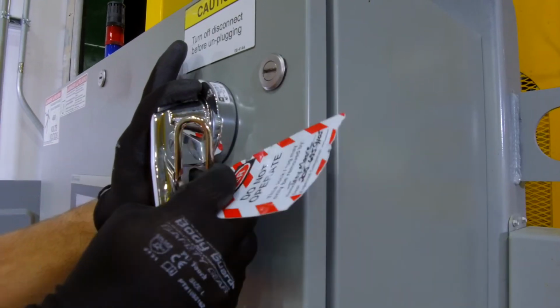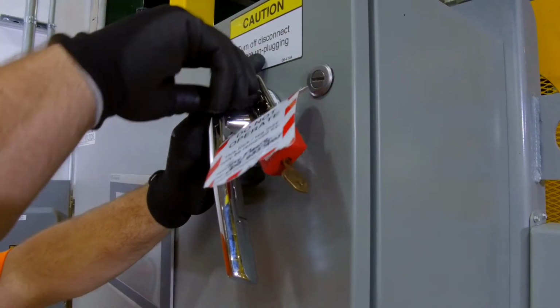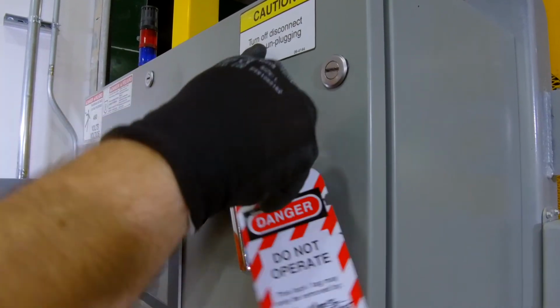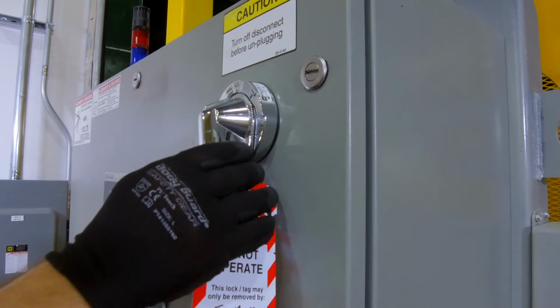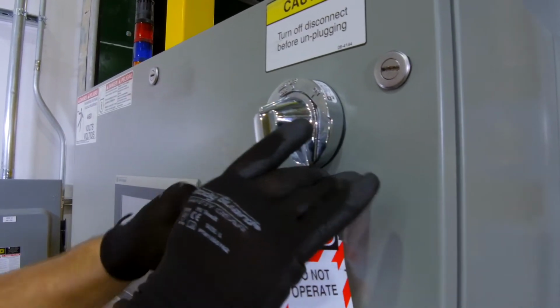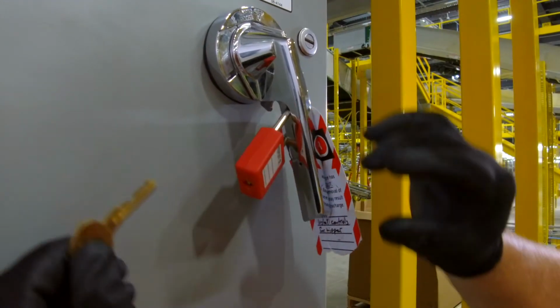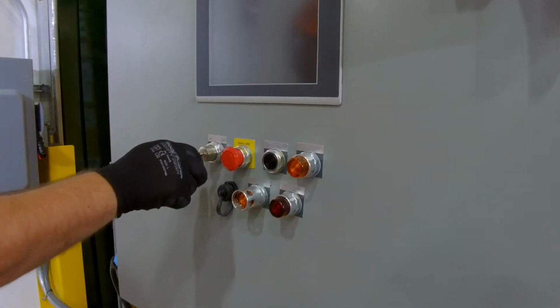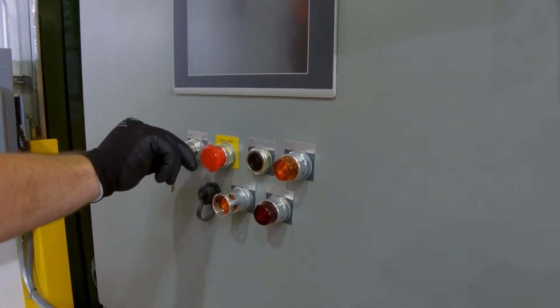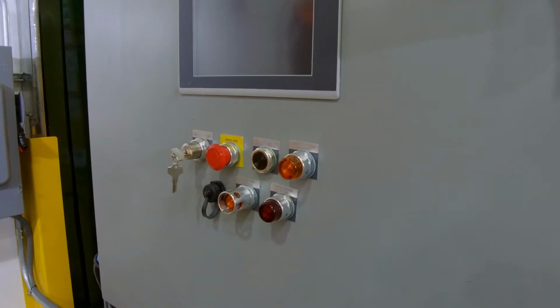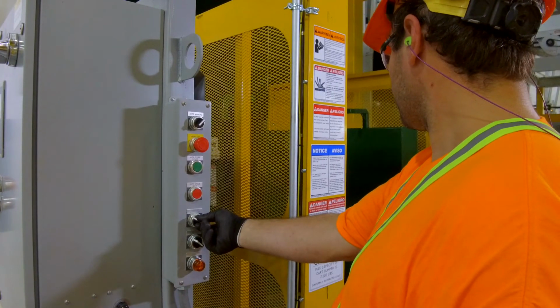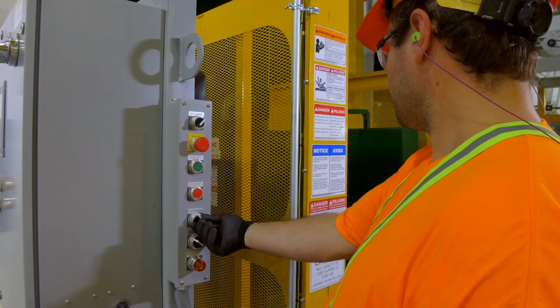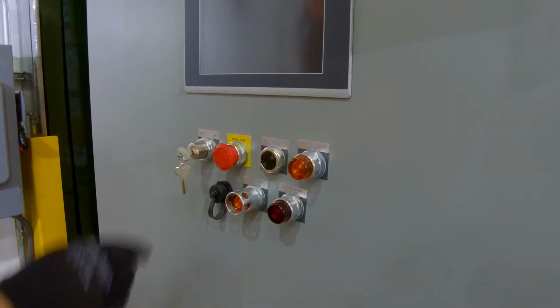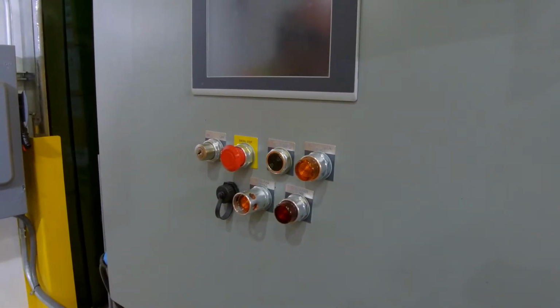Now you can lock out the energy isolating devices by placing a keyed padlock along with an appropriate highly visible warning tag on the disconnect lever. When finished, remove the padlock key and take it with you. After locking and tagging the system, try to start and operate it, as outlined in the operating instructions, to make sure that the lockout tagout is effective. If so, remove the key from the switch and take it with you.